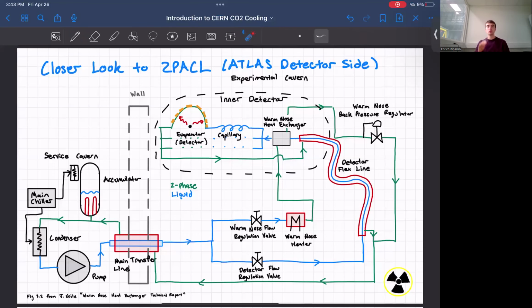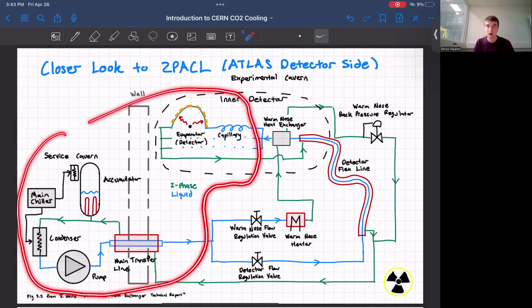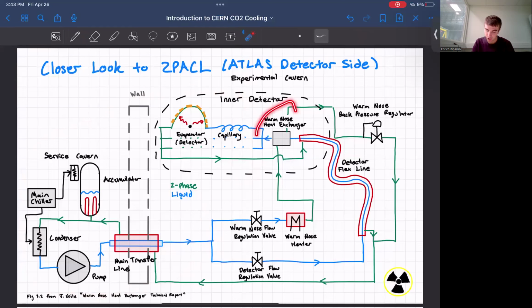Now we'll be giving a closer look into the two-phase plant. These components, which I've circled, we've already seen before. Now we're introducing primarily the warm nose heat exchanger and the detector flex line. The warm nose heat exchanger adds heat, or enthalpy, to the refrigerant before it enters the detector.